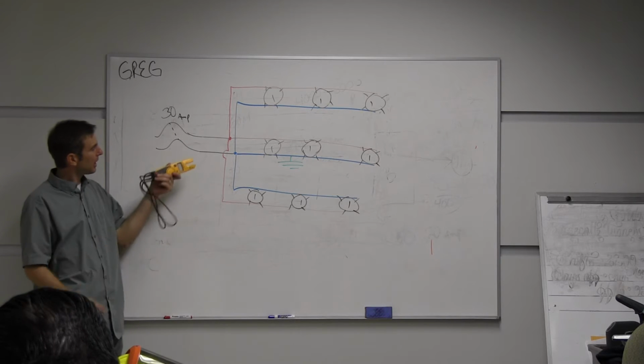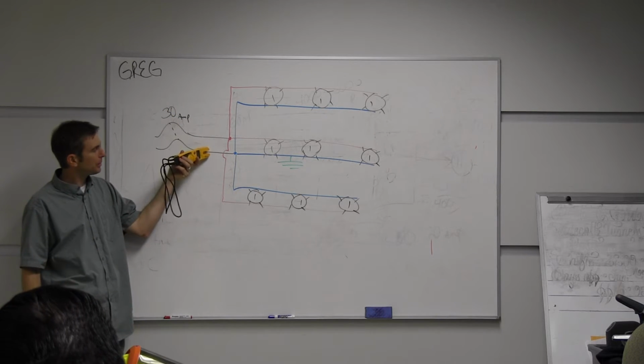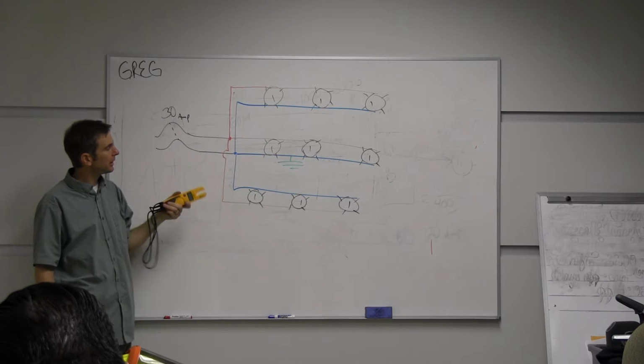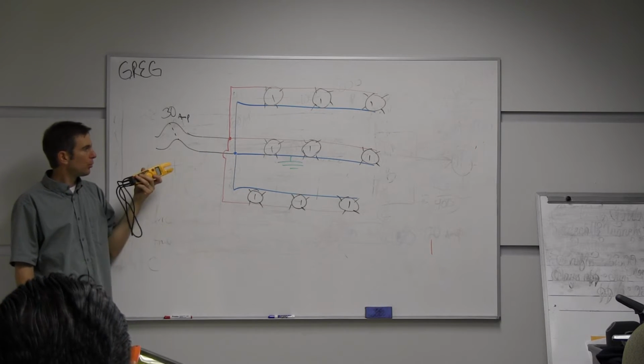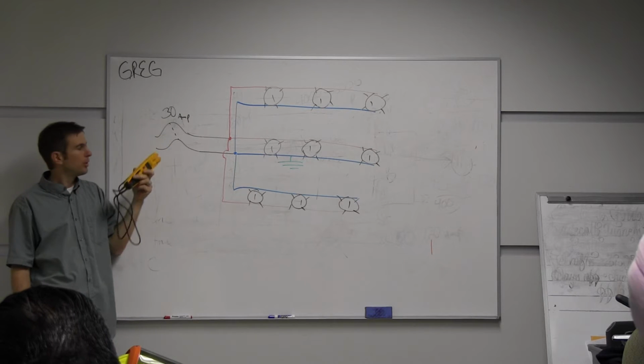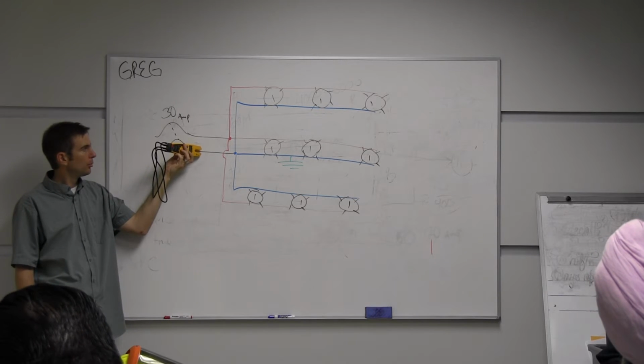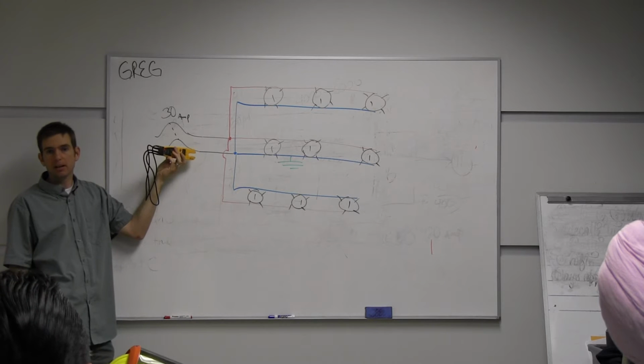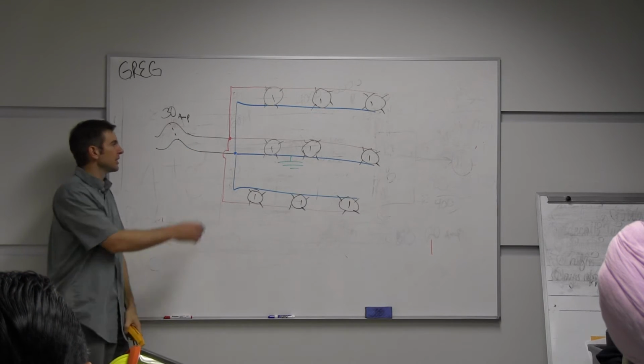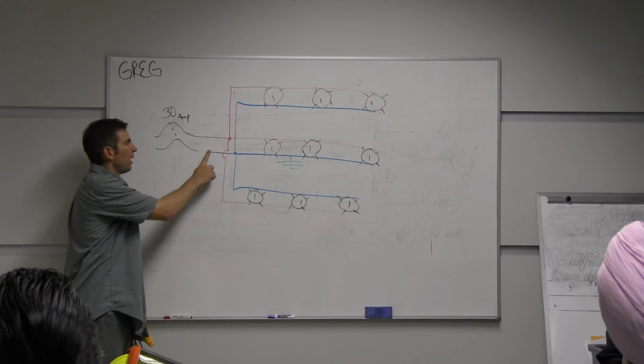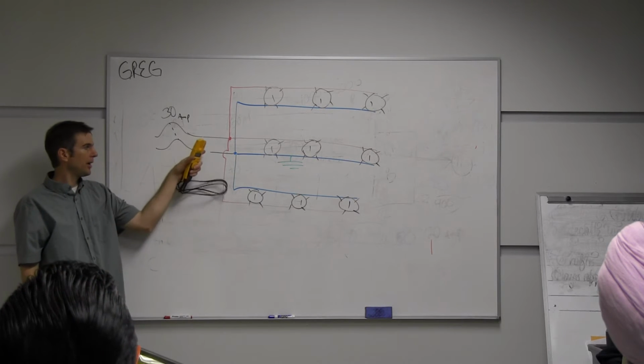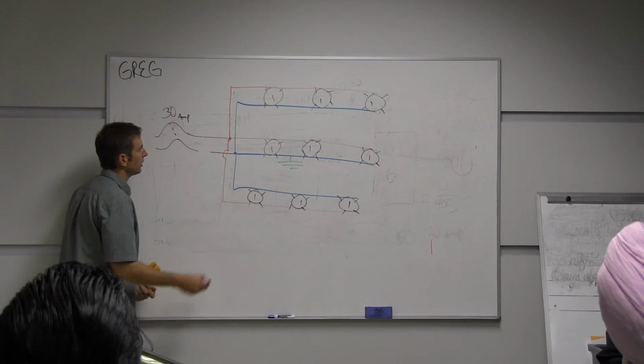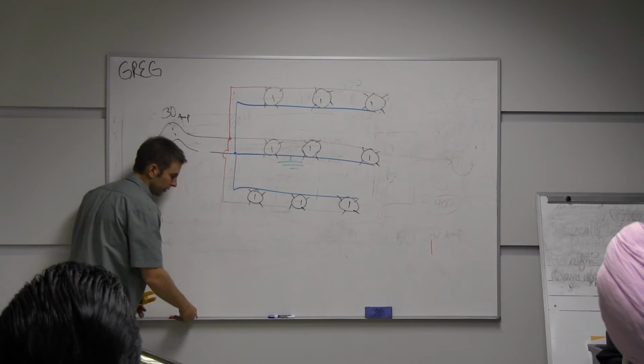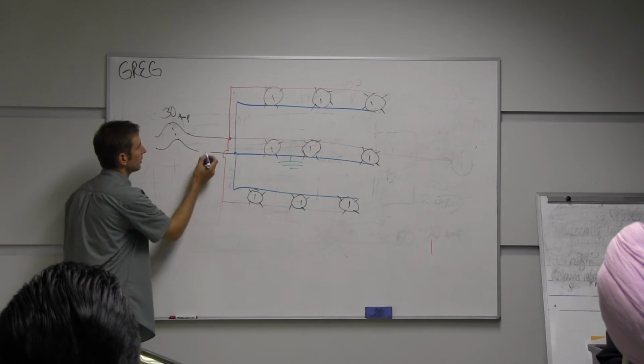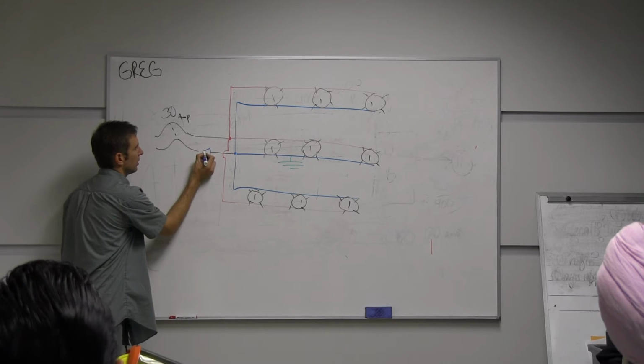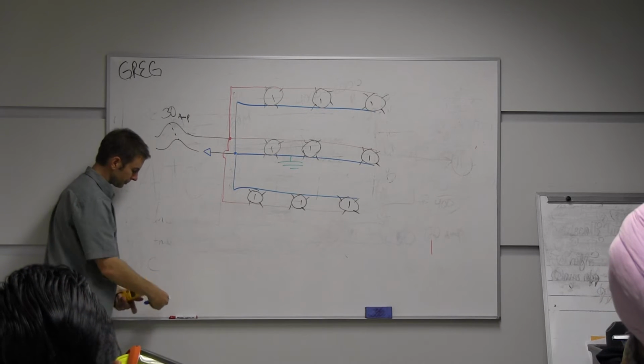All right, so we know we have a problem here. We have over 30 amps. It's tripping the breaker on this conductor, which ends up being our blue wire. But it keeps tripping. We don't want it to trip. We want to be able to troubleshoot this without the breaker tripping, so we can find out where the problem is. What happens if we disconnect the wire from the circuit breaker and put a wire nut on this? If we take this off the circuit breaker, let me put a blue wire nut on it. So we can see that's the blue wire. I put a blue wire nut on it.